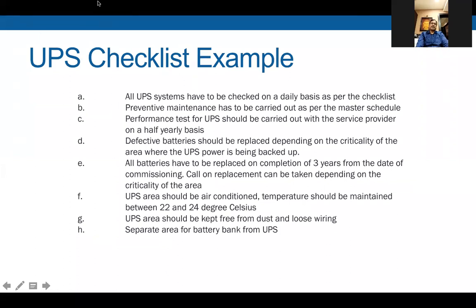So this is a UPS checklist. Again, there have been many incidents in front of me when I have visited the hospitals, as well as it has come in the news about the fire accident. Major culprit is found to be UPSs, which undergo a short circuit. I won't name any hospital in particular, but 2 or 3 hospitals which came in limelight were all UPS fires, where UPS has undergone short circuit and then the batteries started blasting one after another and the fire started going up and the smoke went inside the hospital building all over.